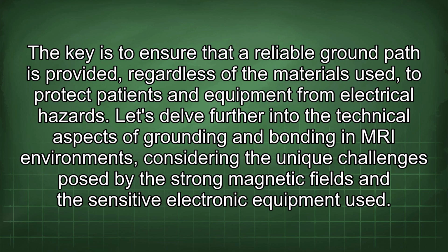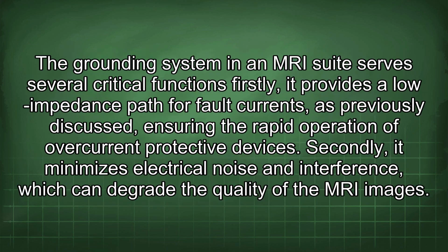Let's delve further into the technical aspects of grounding and bonding in MRI environments, considering the unique challenges posed by the strong magnetic fields and the sensitive electronic equipment used. The grounding system in an MRI suite serves several critical functions. Firstly, it provides a low impedance path for fault currents, as previously discussed, ensuring the rapid operation of overcurrent protective devices. Secondly, it minimizes electrical noise and interference, which can degrade the quality of the MRI images.